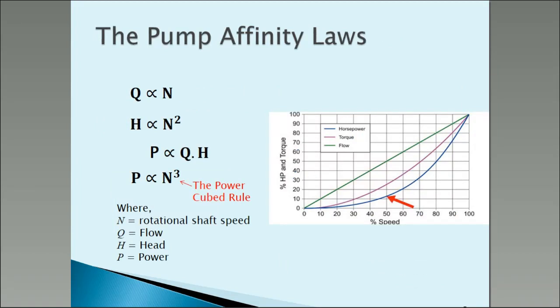We now come straight to the affinity laws, which are the key to understanding how centrifugal pumps work. The first law: Q, the flow, is proportional to speed N. So if we double the speed, we get double the flow. The second law: H, the head or pressure, is proportional to speed squared — related to that centripetal force, the V-squared component or kinetic energy. So pressure is proportional to speed squared. And the power P is proportional to flow times head, and by combining all of these, we get power proportional to N cubed. That's the famous power cubed rule, which applies to wind turbines equally and to pumps as well.